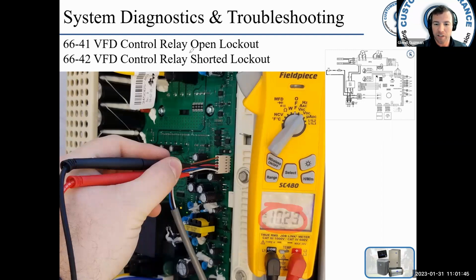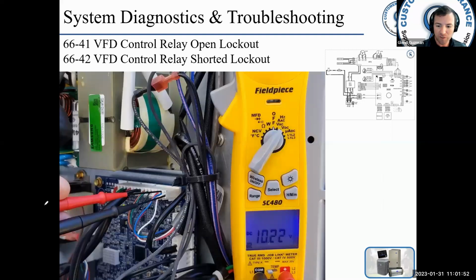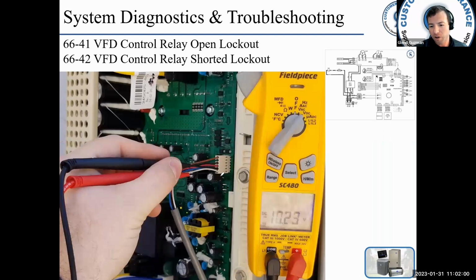But if I suspected an issue with that control relay, then I could always ohm it out. Now, again, to ohm it out, you have to isolate it. So you got to pull this plug off the PCM. Then you can come up here and ohm the VFD control relay. The VFD control relay resistance should be 720 ohms, and that's approximate. If the resistance is much higher than 720, then remove the connector off the VFD and check the pins on the VFD itself.